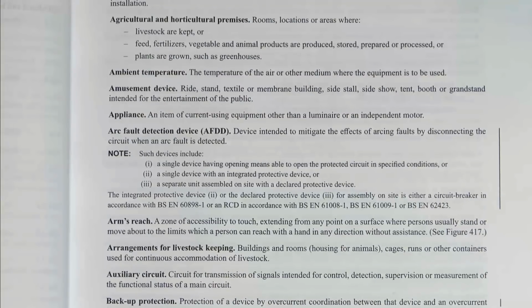The second type, a single device with an integrated protective device, is probably the most common choice you'll find. It's an arc fault detection device combined with, in most cases, overcurrent protection - the equivalent of a circuit breaker - and in many cases the equivalent of an RCD built in as well. That's pretty much most of what you can actually buy at the moment - RCD, circuit breaker and arc fault detection all built into the same single unit.